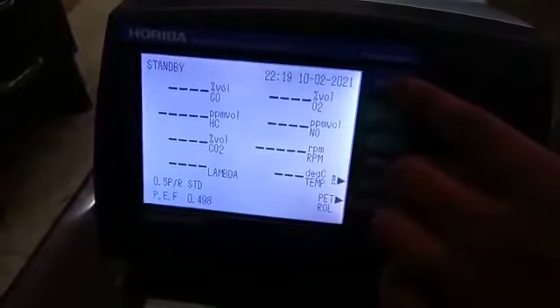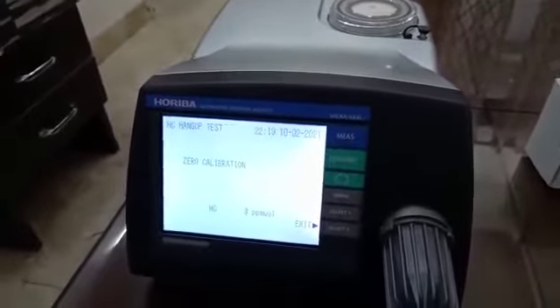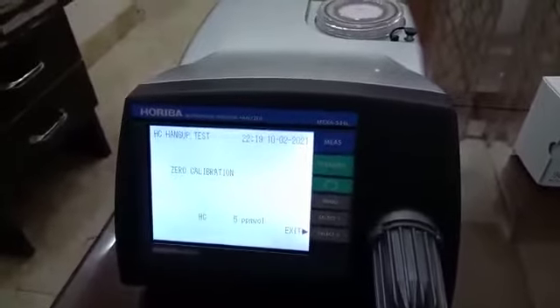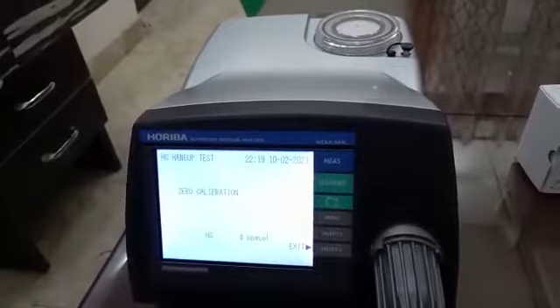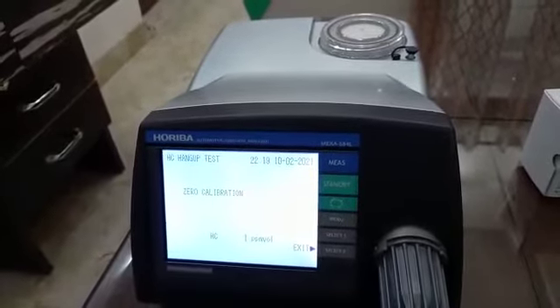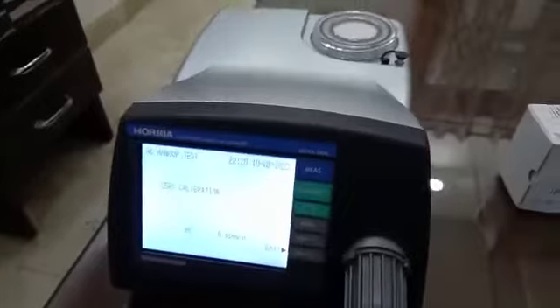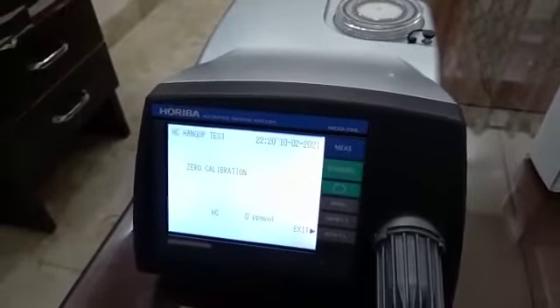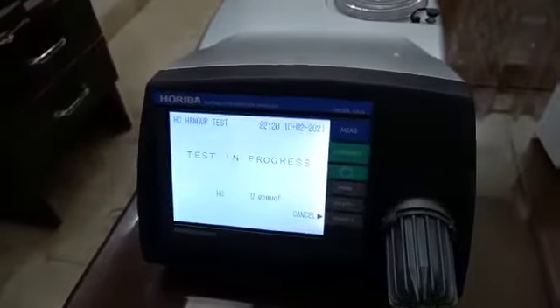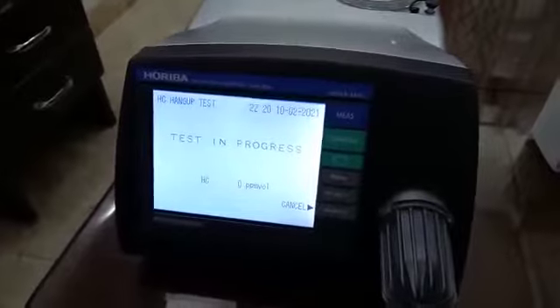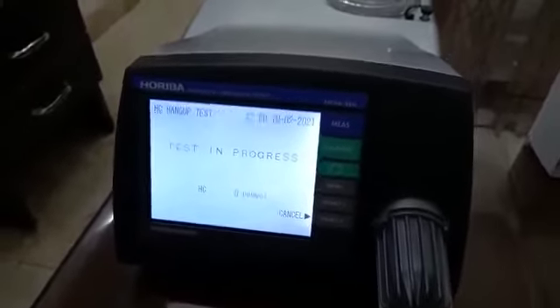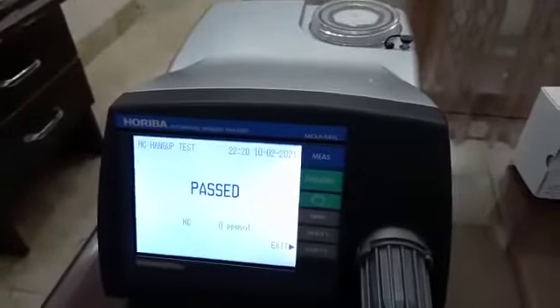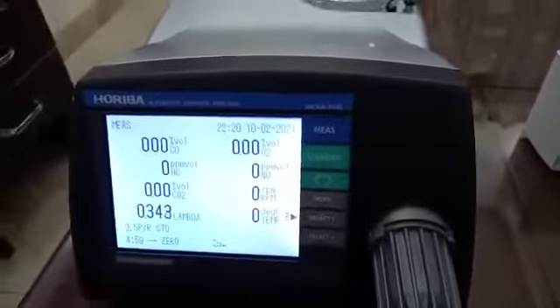So whenever we press the measure button, measurement will start, and prior to the measurement, the machine will verify itself for the HC hang up test, and there will be zero calibration. Zero calibration is basically done to ensure the lower point of any kind of calibration. Like suppose you are measuring 10 ppm of gas. In 10 ppm of gas, 10 ppm is the high one, so you are calibrating with the span. It means the higher value. Then what about the lower value? For the lower value, we need to verify and calibrate via zero calibration. Now it's getting passed, and now you can see the measurements.